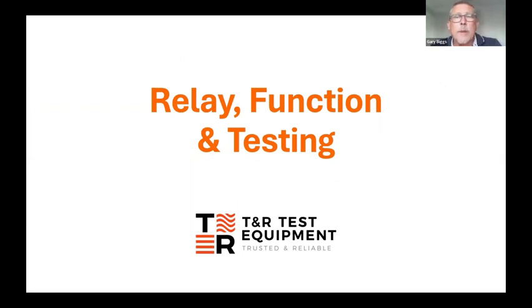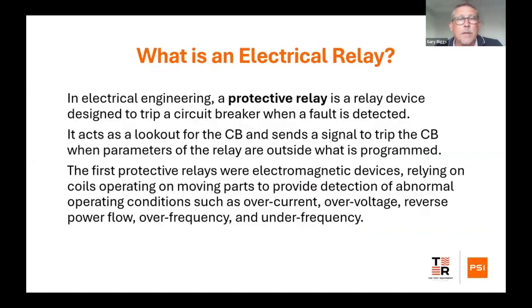So what we're going to do is talk about relay testing, relay function and testing. What is a relay? Where does it fit into a system, and how do you test it correctly to ensure that you've got protection on a system? So in electrical engineering terms, a protective relay is a relay device designed to trip a circuit breaker when a fault is detected. It effectively acts as a circuit breaker lookout.